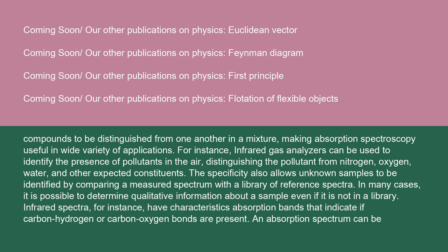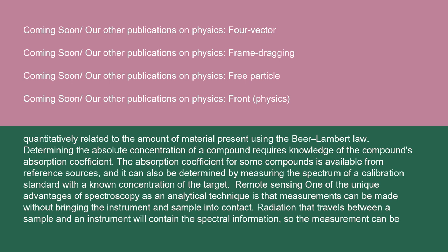An absorption spectrum can be quantitatively related to the amount of material present using the Beer-Lambert law. Determining the absolute concentration of a compound requires knowledge of the compound's absorption coefficient. The absorption coefficient for some compounds is available from reference sources, and it can also be determined by measuring the spectrum of a calibration standard with a known concentration of the target.